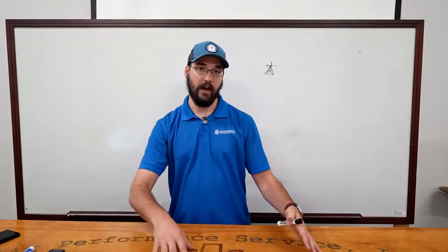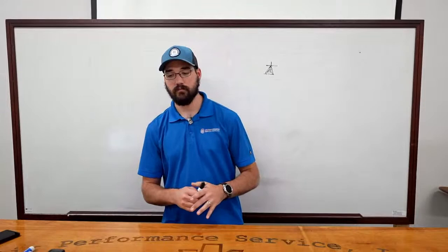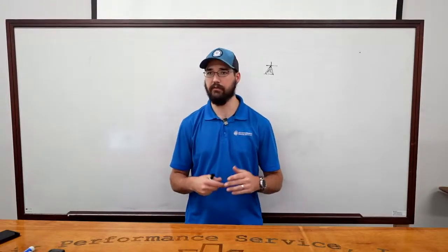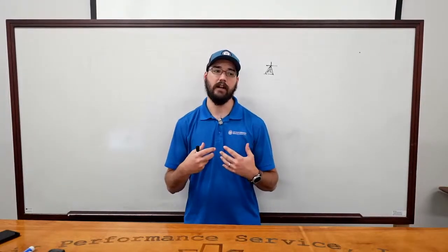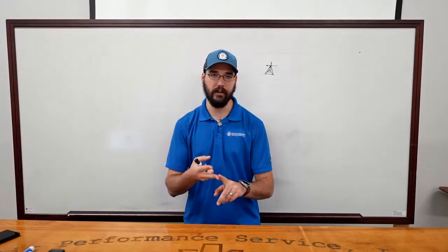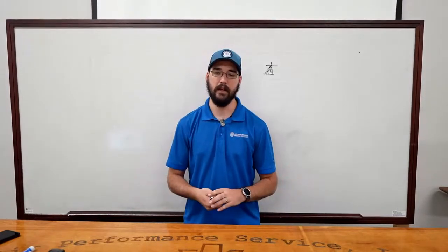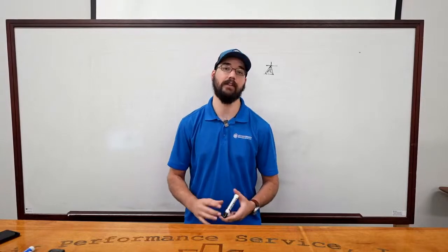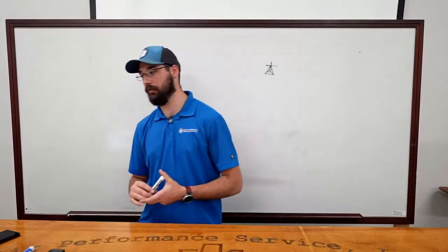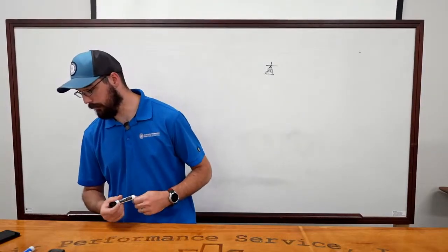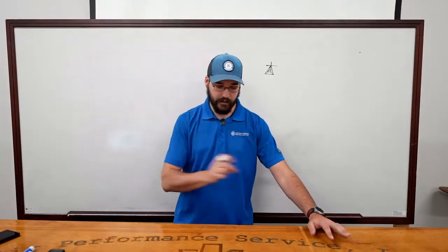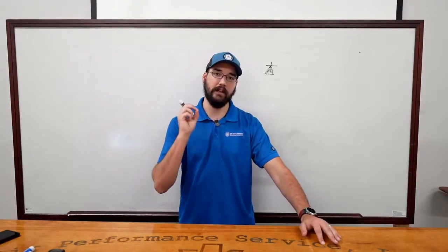And if you're outside of that range with a diode, then it's very likely that you're having some kind of, whether it be a weak gate, you're having a leak to ground, something is happening. And then we use a ton of DC in these systems, and so your ability to read that accurately is going to be critical. The other really big recommendation I have is take it slow.